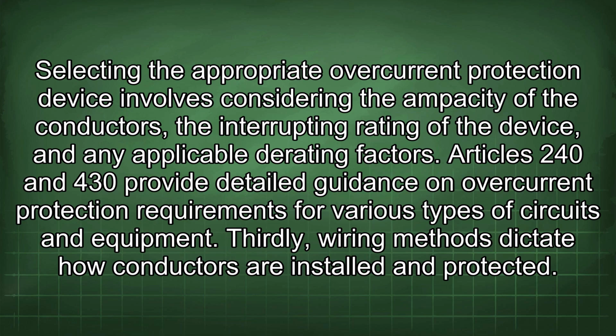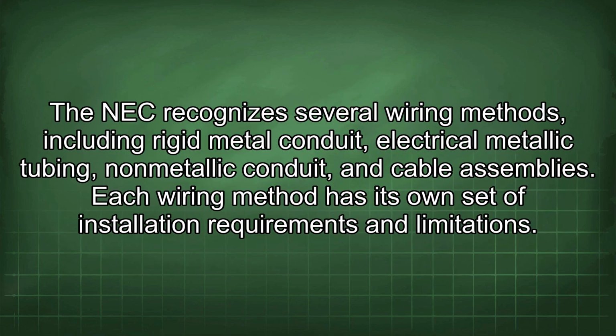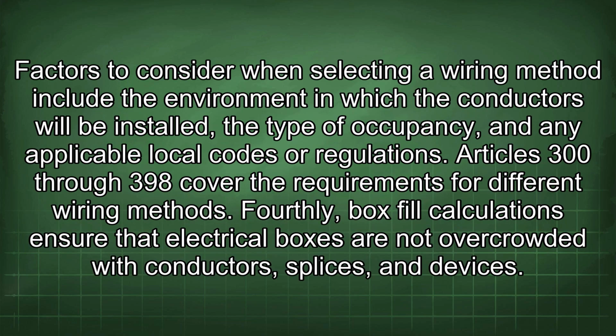Thirdly, wiring methods dictate how conductors are installed and protected. The NEC recognizes several wiring methods, including rigid metal conduit, electrical metallic tubing, non-metallic conduit, and cable assemblies. Each wiring method has its own set of installation requirements and limitations. Factors to consider when selecting a wiring method include the environment in which the conductors will be installed, the type of occupancy, and any applicable local codes or regulations. Articles 300 through 398 cover the requirements for different wiring methods.